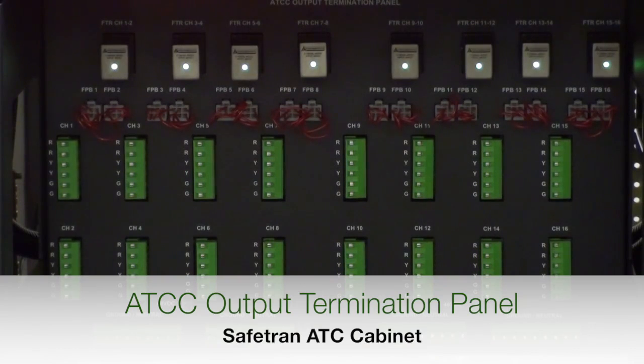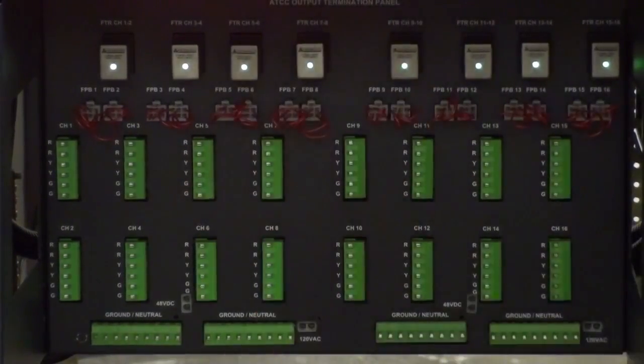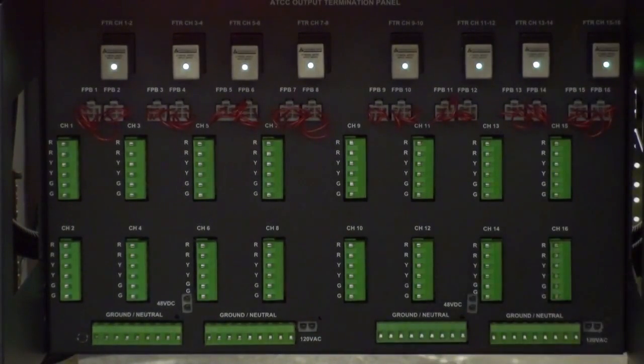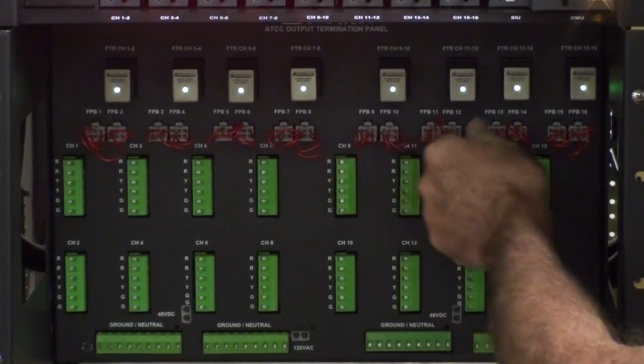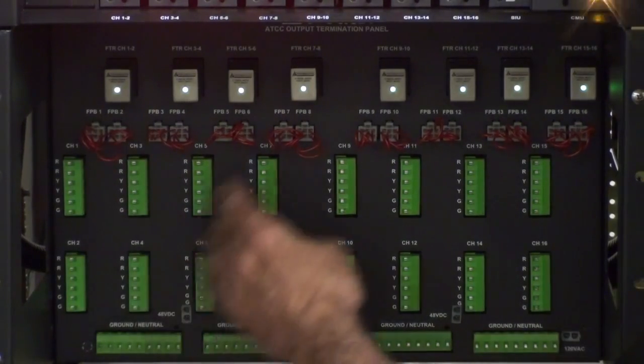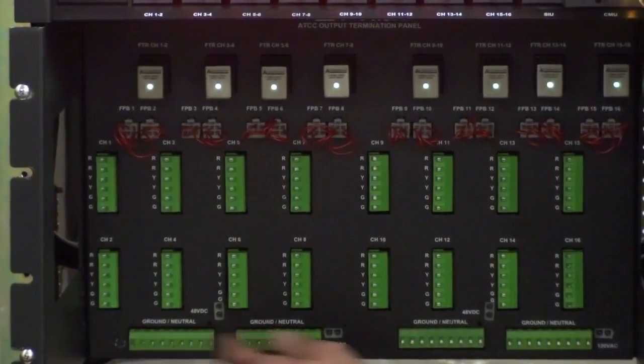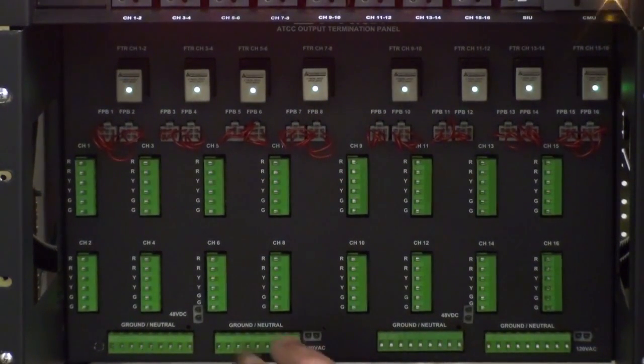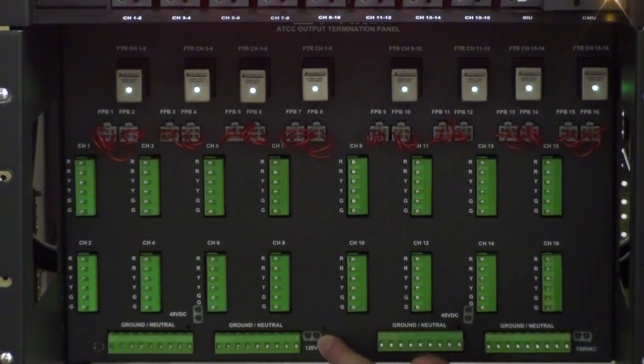Here is the output termination assembly. At the top are the new high-density flash transfer relays. Each relay includes an LED to indicate when it is active. The LED is activated through a third relay contact so that it will not light unless the relay has actually closed. Below the flash transfer relays are the new miniature flash program blocks. Below the program blocks are the pluggable Euro-style field wire terminal blocks. Along the bottom are the ground or neutral terminal blocks, configurable for 48-volt or 120-volt operation. Also included are these 48-volt DC and 120-volt source outputs that enable the field technician to apply power to the signal heads and confirm proper operation before the load switches are installed. Each output termination panel supports 16 channels.